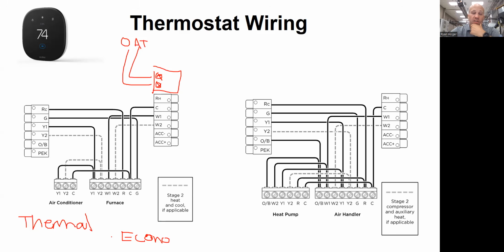So once I know that outdoor air temperature from my calculations, then I tell my thermostat that temperature. And I think we had a screen that showed it last week. We'll tell it whatever that temperature is. Let's say it's 38 degrees for this particular project. So at 38 degrees, the thermostat says, hey, if it's above 38 degrees, I'm running the heat pump. Let's go, heat pump time. And if it's below 38, I'm shutting the heat pump off and I'm running the gas furnace, because that's the number you told me to switch it over at.